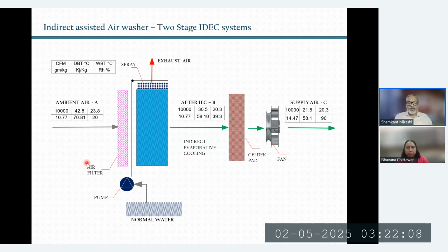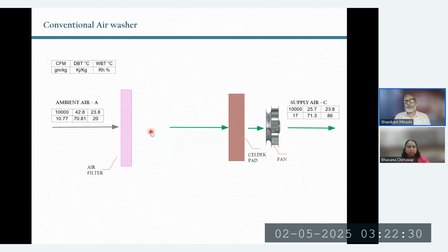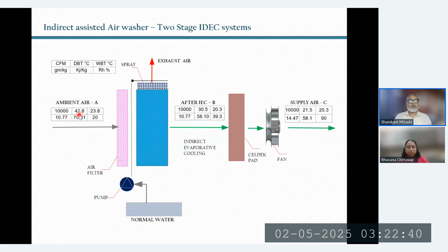So today if somebody asks us for a ventilation system, we can offer a cooling system with two cooling stages. The second stage continues to be the same cooling media. What we add is an air-to-air heat exchanger, which is homegrown with proprietary features. The enhancement we've achieved: if you remember these numbers, we were able to cool 42-degree air down to about 25 degrees before. Now, with the same input conditions, we can cool it down to about 21-22 degrees. We've achieved a delta T between incoming and outgoing of almost 20 degrees.